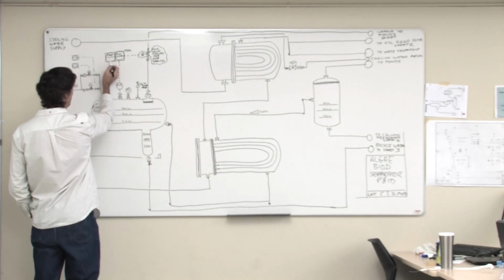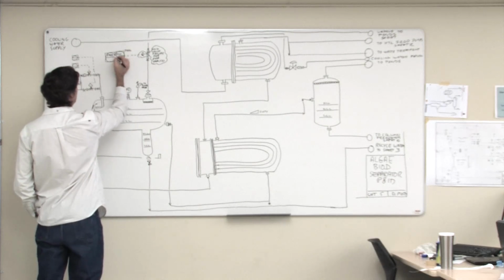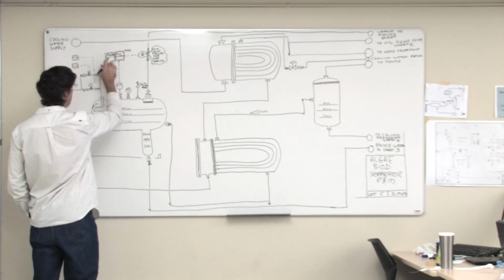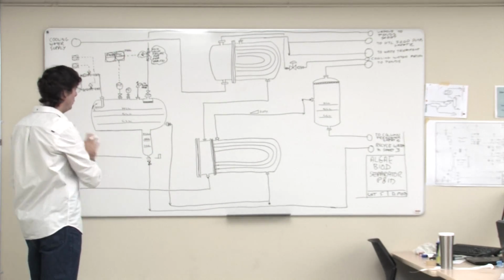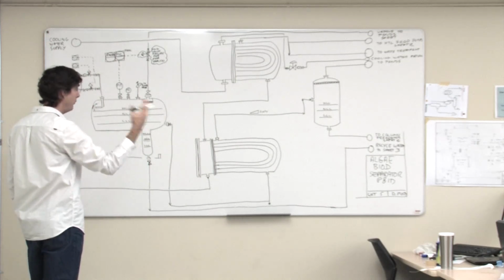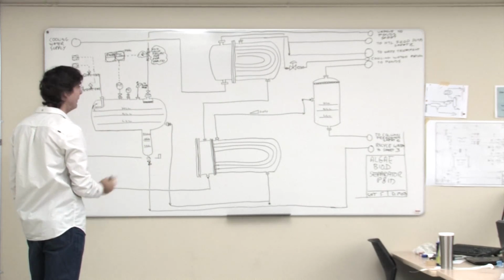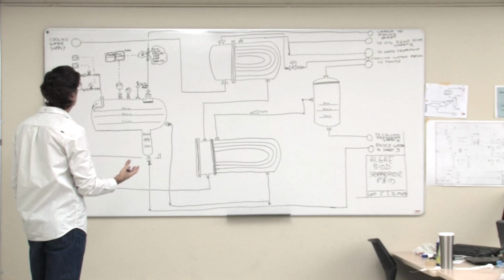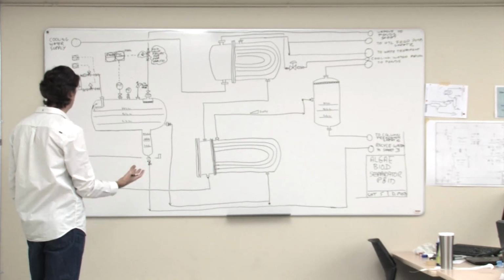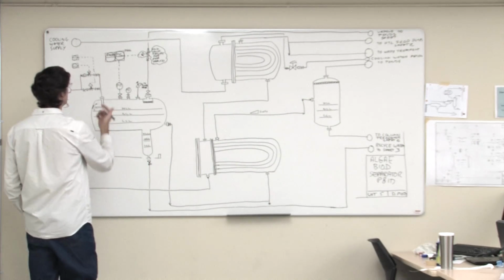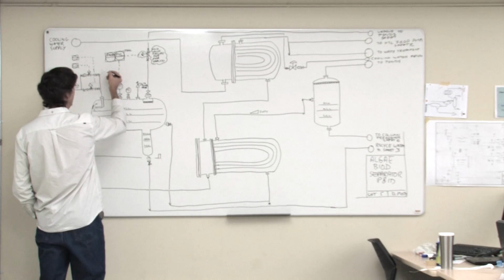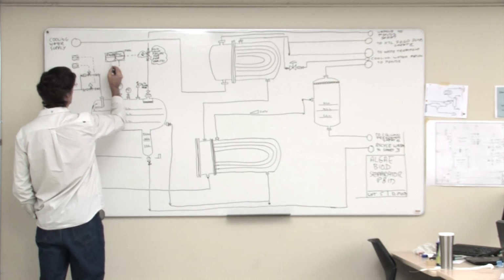So let's say we want that - say we have a high alarm and a high-high, and when it hits the high-high, we want to have some sort of trigger in the control system. Maybe we want to shut down the feed pumps, maybe we want to shut the heat off somewhere. If that's the case, then essentially we're really building an interlock system at that point in time, but we're doing it with a basic process control system.